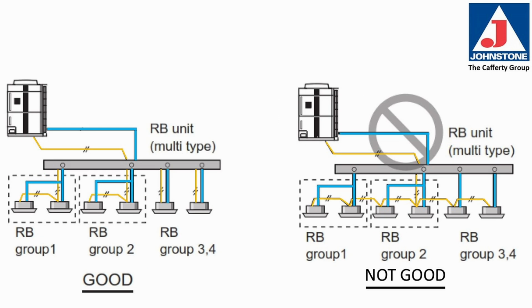This is an example of a multi-type refrigerant branch unit. You'll see the good section on the left. Group 1 is wired and piped to one port of the branch box. Group 2 is wired and piped to one port of the branch box. Group 3 and 4 are wired each to individual ports of the branch box and piped to each port of the branch box. So when that unit calls for cooling or heating, it knows which valve to open. The system on the right, again, as in the last example, we have a daisy chain of all of the indoor units, so the system would become really confused not knowing which ports to open when there's a call for refrigerant from an indoor unit.